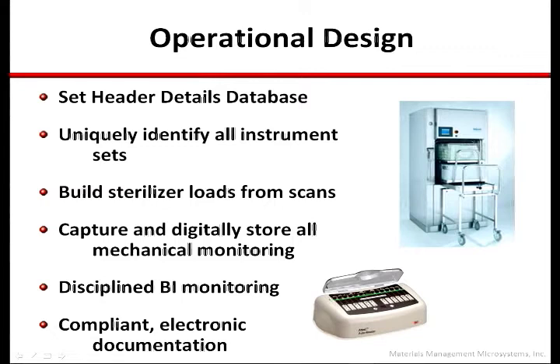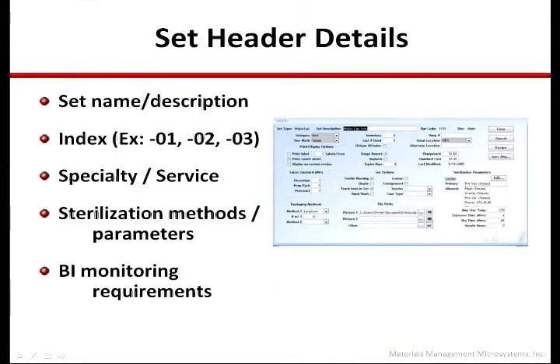Following the assembly and packaging process, the uniquely identified items are scanned as part of the sterilizer load build. The system will also prompt the use of BI process challenge devices per load contents or department procedures. Following sterilization, the system will prompt and discipline all aspects of the monitoring sequence, and will fully automate all aspects of BI-related documentation. Finally, the system is designed to alert potential recall scenarios based on the results of both test and control BIs back to the previous known negative BI for the sterilizer in question.